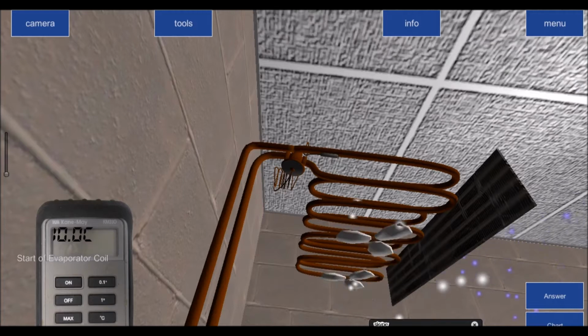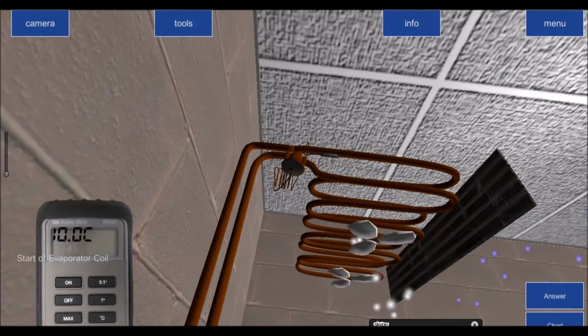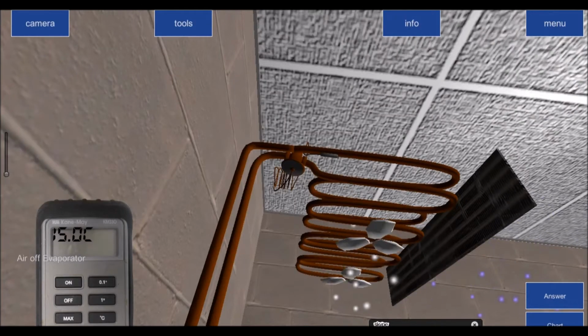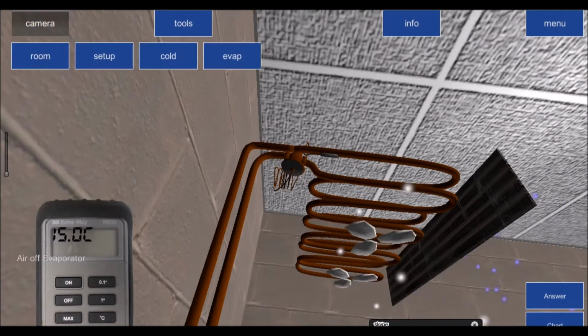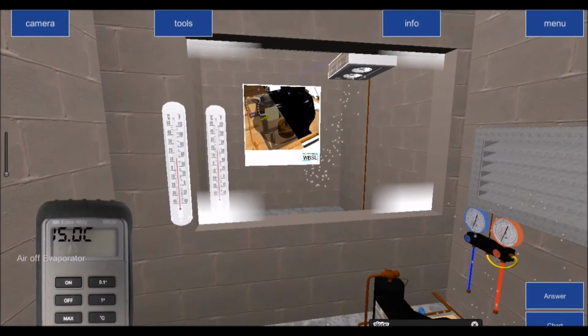So it's 10 degrees lower than the air on temperature. It can be as little as 5 degrees less and as much as 10 degrees less, or anywhere in between. In this particular scenario, it is 10 degrees lower. That's within the norm. Therefore, we can say with confidence, is LP too low? No, it's normal. It's within the operating range. So the next question we look at is, is HP too low? HP stands for head pressure, condensing pressure. Again, in order to answer that question, we need to determine what is the normal condensing temperature for the ambient condition that the condenser is located in.